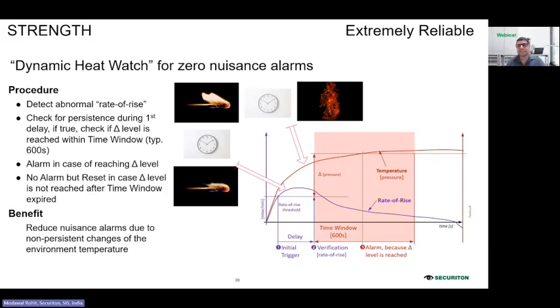So you can easily see if there is a slow increase due to the opening of a door or because of a spark, and it goes down. You will see a spike or a high in the software, but it will not give you an alarm because it does not last for a longer period of time. All of a sudden it creates a spike and then it goes back. But on the software you will see there is a problem at that time, and you can take necessary actions.